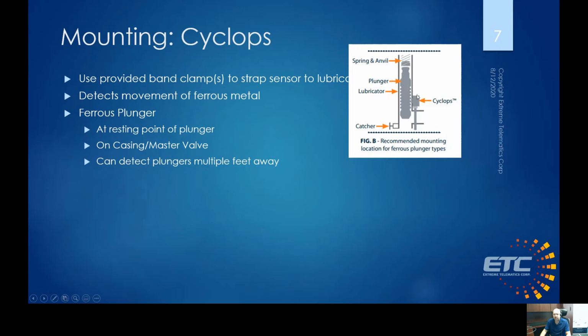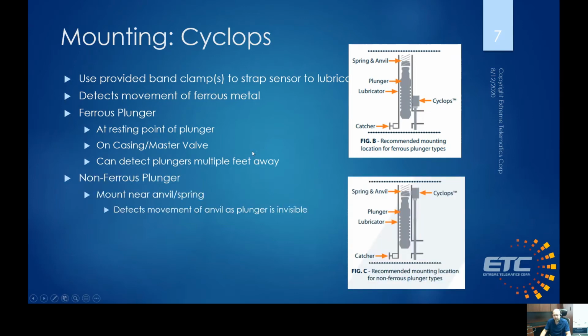And because the Cyclops is one of the most sensitive sensors out there, you can actually put it on the casing or on the master valve. You can detect the plunger multiple feet away. So you've got a lot of flexibility in where to put the Cyclops. It doesn't have to be at the bottom of the lubricator. It doesn't have to be in one specific spot. It'll work pretty much anywhere when you're working with a ferrous plunger.